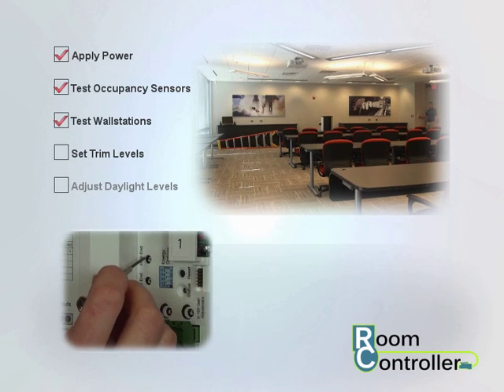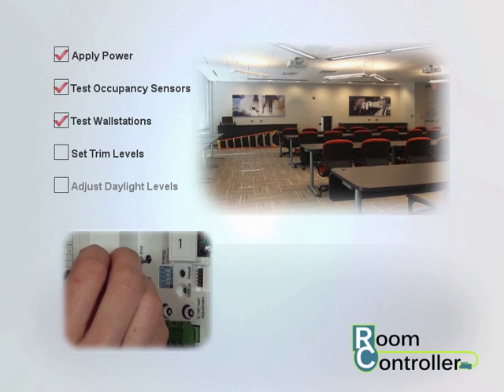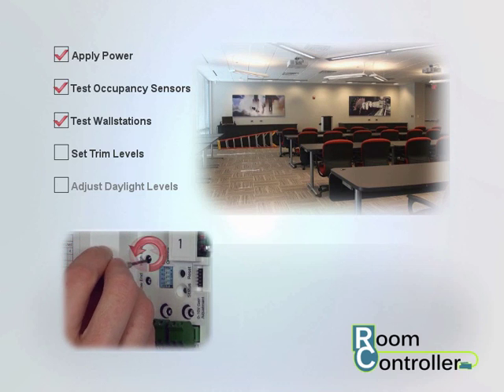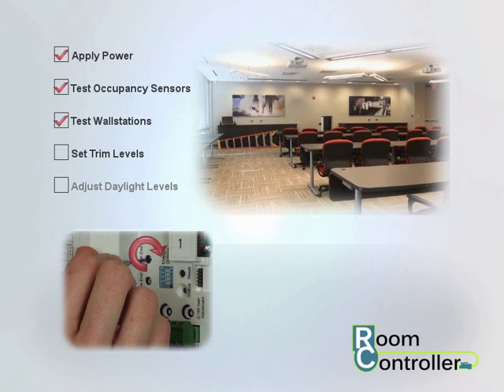Using a small screwdriver, twist the maximum trim dial counter-clockwise and then fully clockwise again. The lights will go full bright and the room controller will enter adjustment mode.